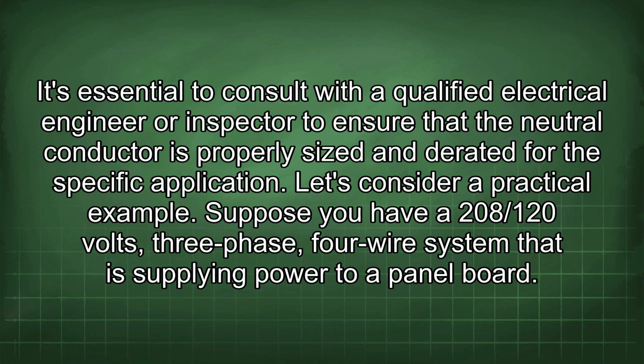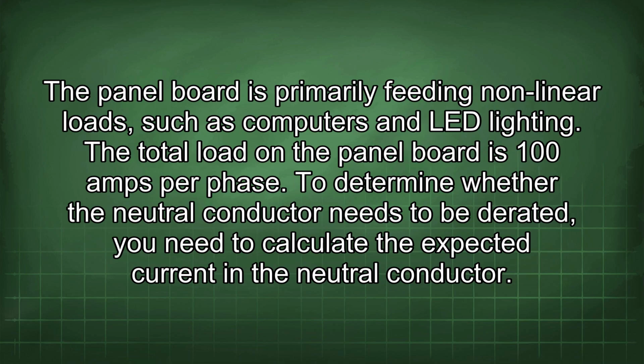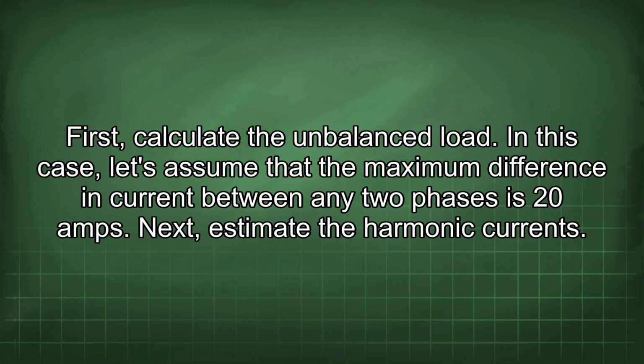Suppose you have a 208/120 volts, three-phase, four-wire system that is supplying power to a panel board. The panel board is primarily feeding nonlinear loads such as computers and LED lighting. The total load on the panel board is 100 amps per phase. To determine whether the neutral conductor needs to be derated, you need to calculate the expected current in the neutral conductor. First, calculate the unbalanced load.